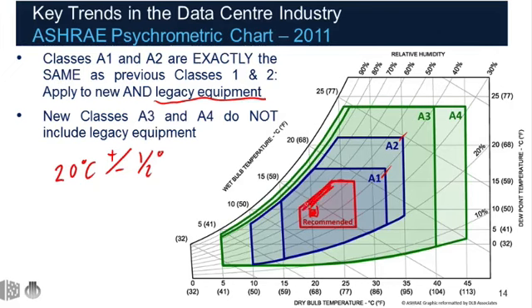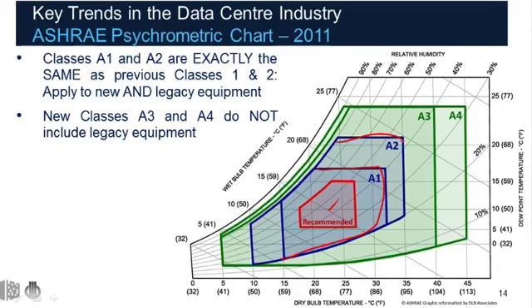This whole recommended area, we can be anywhere we want in this envelope, and we define the rate of change in this envelope as well. All the equipment manufacturers make, they test it to the recommended level, which is a reliability and energy performance statement, and then they also test it to whatever allowable rating that piece of equipment is. Of course, the larger the envelope, A1, A2, A3, the bigger the opportunity for using an economizer and the amount of economizer hours.